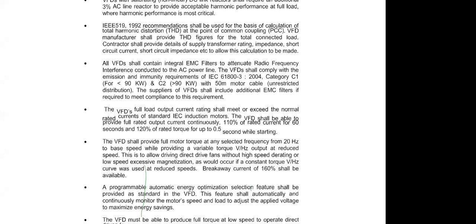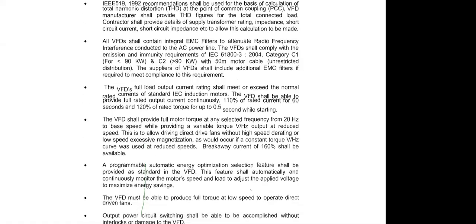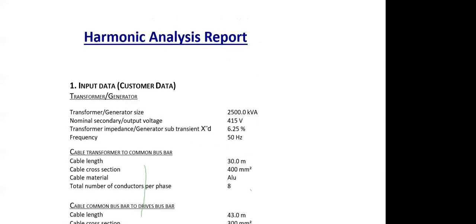And you will be surprised, if not known, that a normal VFD without harmonic precaution creates 38 to 39% distortions or ripples in the system. So if you don't need this elimination, it is fine. But it is of course your prerogative to ask the VFD manufacturer what product they are offering and what distortion they are offering you. There is an analysis of how it is calculated and how it is done. There is a harmonic analysis report, how it looks like.